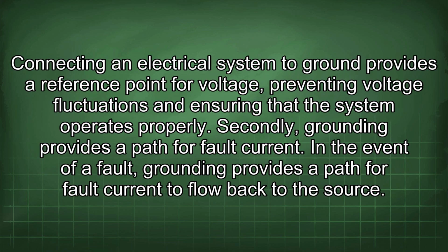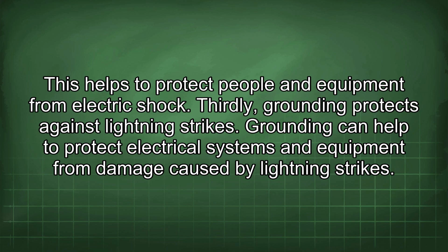Connecting an electrical system to ground provides a reference point for voltage, preventing voltage fluctuations and ensuring that the system operates properly. Secondly, grounding provides a path for fault current. In the event of a fault, grounding provides a path for fault current to flow back to the source. This helps to protect people and equipment from electric shock. Thirdly, grounding protects against lightning strikes. Grounding can help to protect electrical systems and equipment from damage caused by lightning strikes.